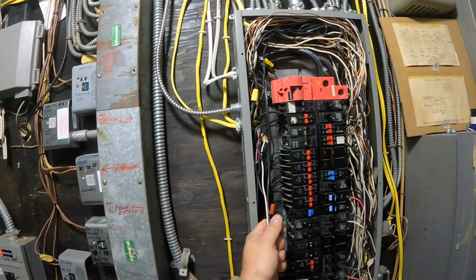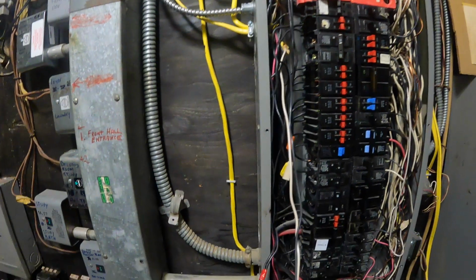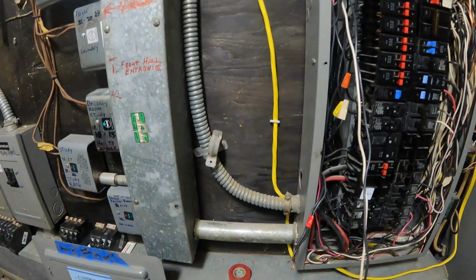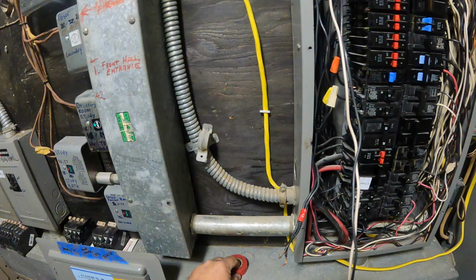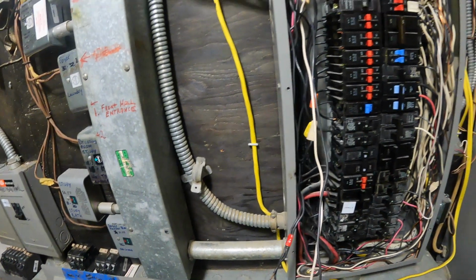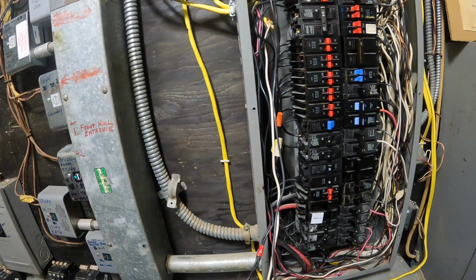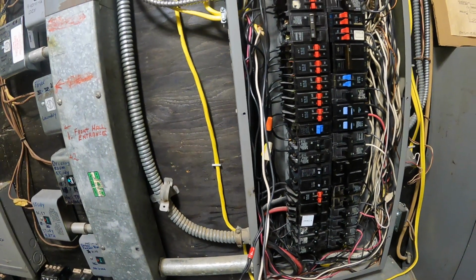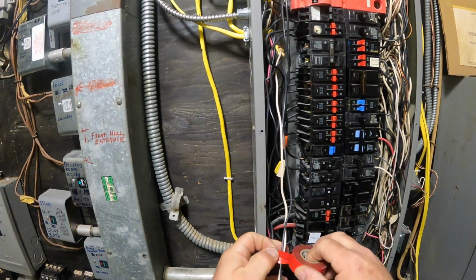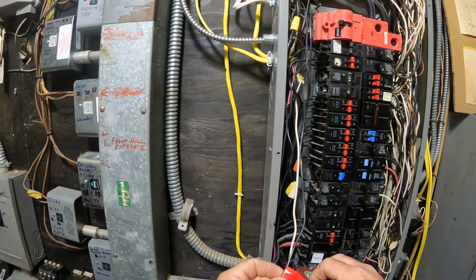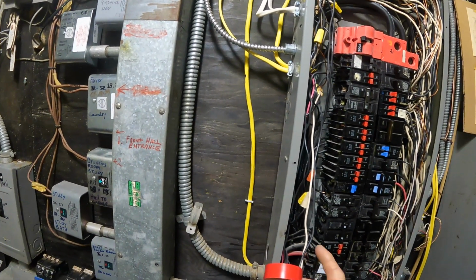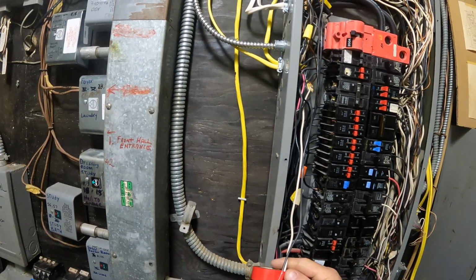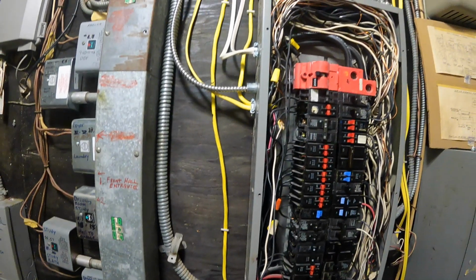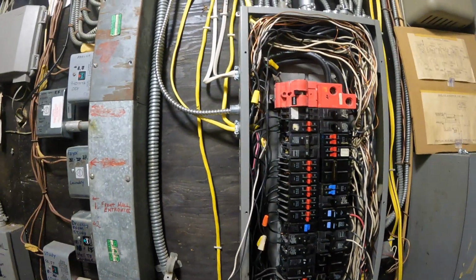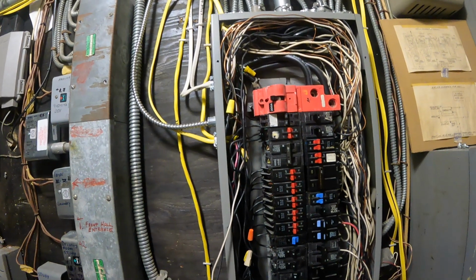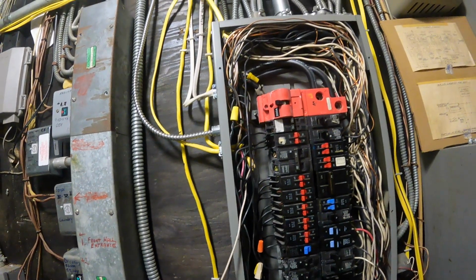So as you can see here, I have a double pole circuit. All right, so they never identified that white conductor, which by code needs to be re-identified as a hot conductor. Anything but green, gray, or white would be acceptable. And the other two wires you see below there with the red tape. So what I'm doing is I'm taping the two conductors together that make up the double pole circuit. So when I take these cables out of this panel, I know what they are when they go back into the new panel, and they'll get a double pole breaker.